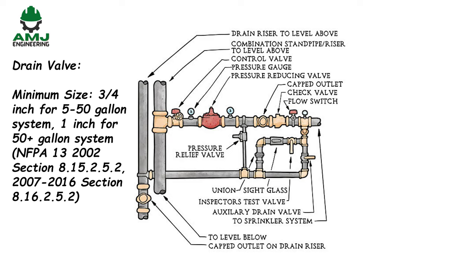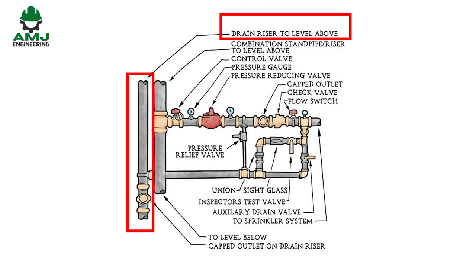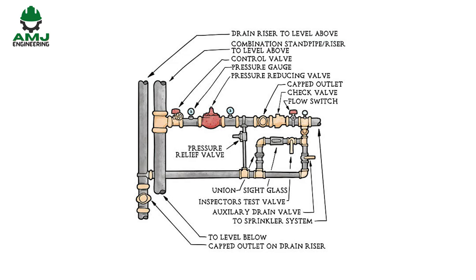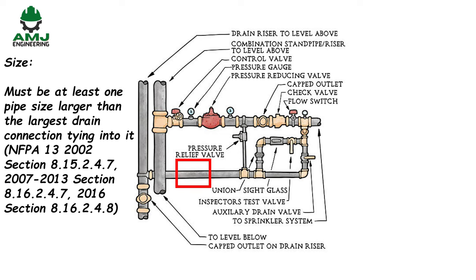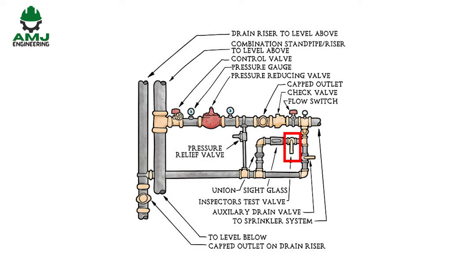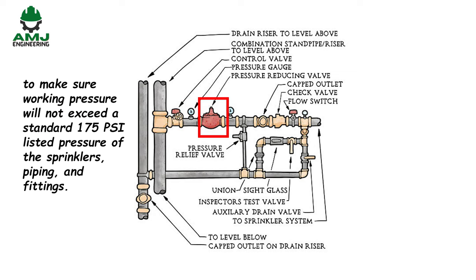Drain valve minimum size: three-quarter inch for five to 50 gallon systems, one inch for above 50 gallon systems. Drain riser discharge must be to outside or to a drain capable of handling the flow, and must be at least one pipe size larger than the largest drain connection tying into it. Inspector's test must be accessible and discharge outside or to a drain capable of handling flow, and must be downstream of the water flow alarm. A pressure gauge is required at each floor control valve.